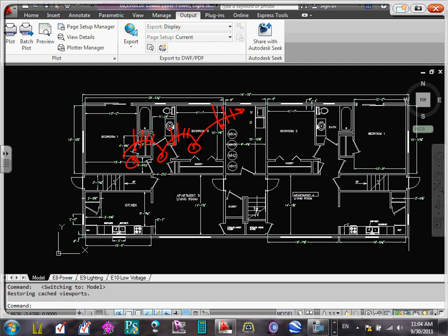So where do I need them? I need smoke detectors in bedrooms and hallways. Only the hallways open to bedrooms; I'll talk about the common hallways in a second here. One system for each apartment, interconnected with 14/3. That's what we did, 14/3, because the signal has to go on one. Fed from a lighting circuit. I'm asking you guys to feed it from a lighting circuit in the area, not a dedicated circuit.